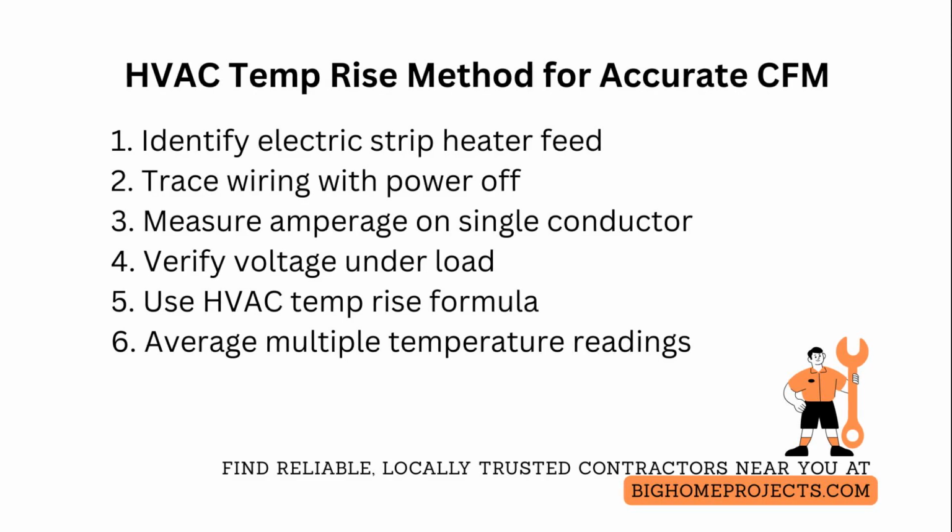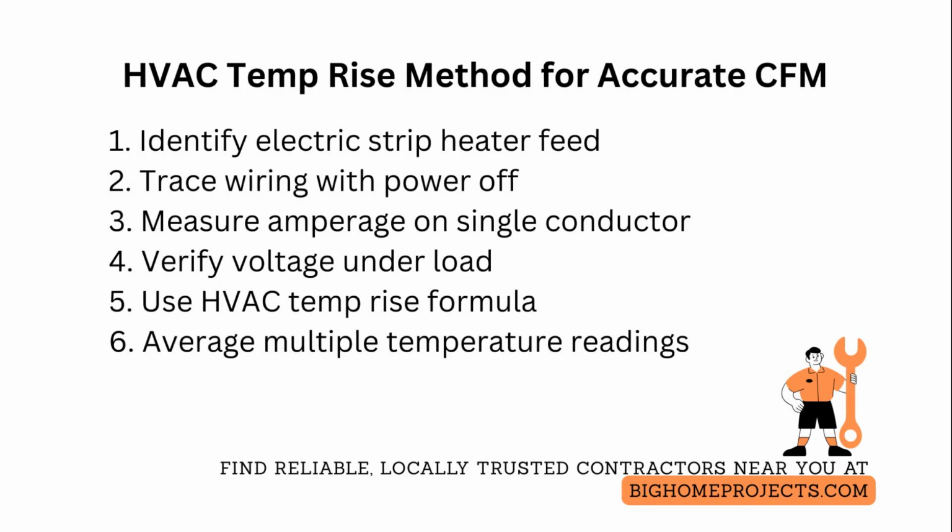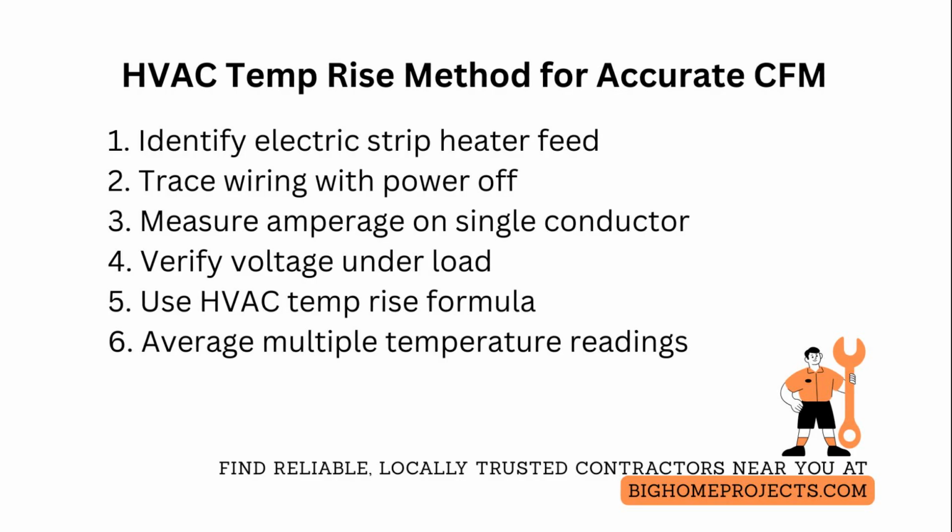temperature at the supply and return grill with a calibrated vane or thermocouple probe inserted into the airstream for steady readings. Average several temperature pairs over 1 to 2 minutes to avoid transient spikes caused by cycling. Start with the system at steady state and with staging heaters fully on if the unit has multiple stages.